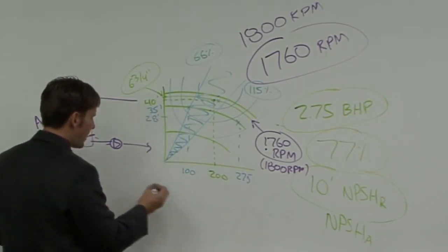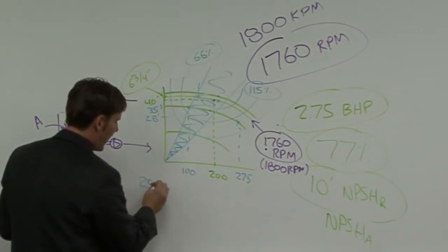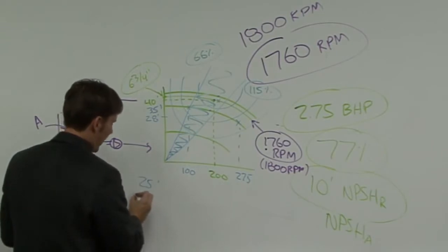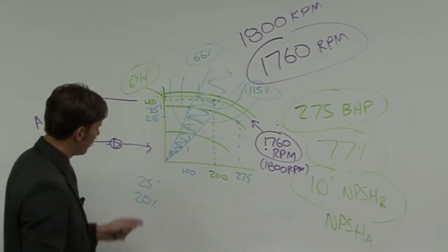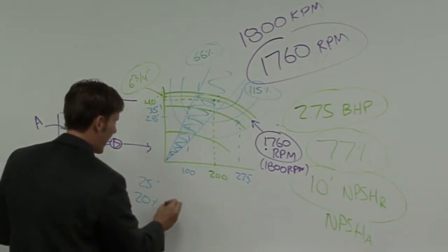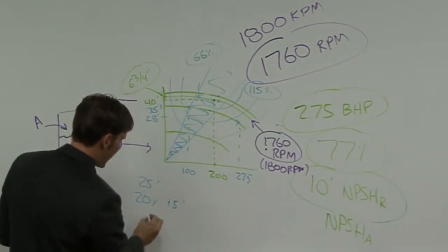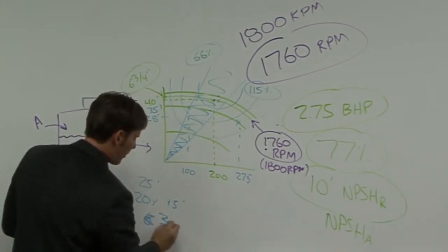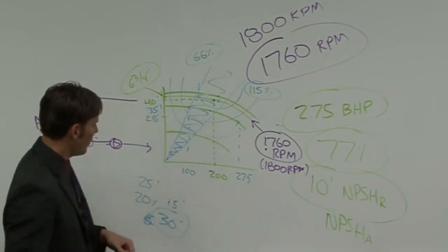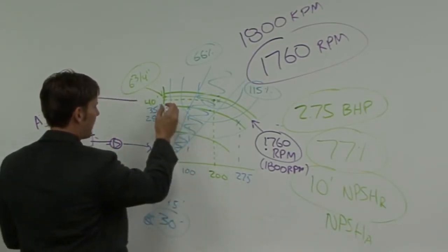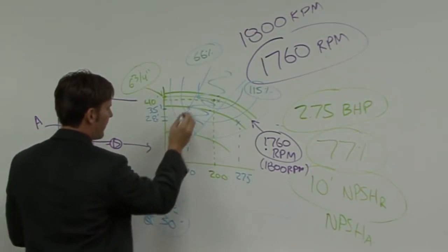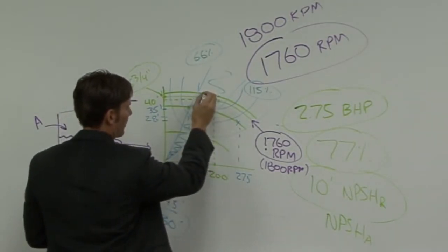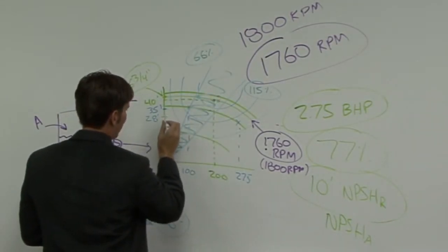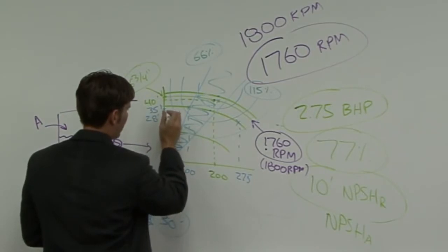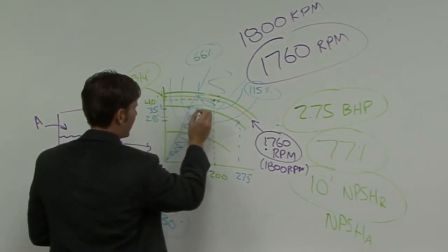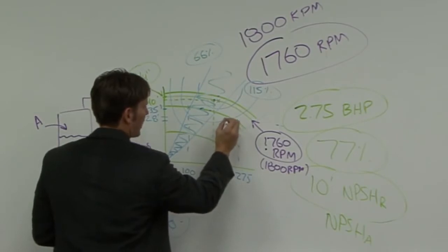So they calculated 25 feet of head, but they put about a 20% safety factor on it. Well, 20% of this would be an additional 5 feet. So now they're going to size their pump for 30 feet of head. Well, in reality, they don't have 30 feet of head. They only have 25 feet of head. And what's that going to do on the pump curve? We'll draw a new pump curve right here. Instead of operating here, they could operate out over here.